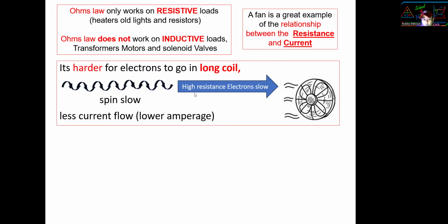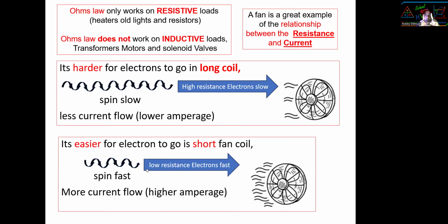It's harder for the electrons to go through a long coil with a fan. Again, with a long coil like this, it's going to take a long time for this fan to spin; it makes it go slow. But now if I have a small winding on the motor, it's going to spin fast. This is important to understand because later when I cover the compressor, the run winding and start winding of the compressor, we will know why the run winding is a lot smaller, usually 1.2, 1.5, than the start winding, which is way larger. That's later on when we cover compressors and compressor windings. But it's important to understand that a fast speed motor has less resistance than a slow speed motor.